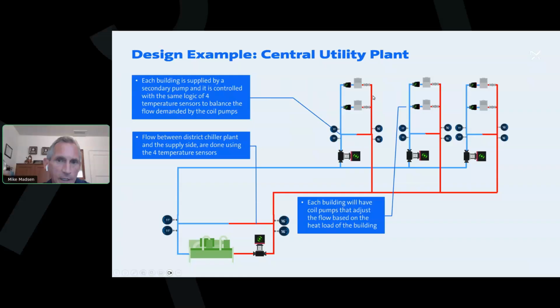So if we converted this close building to distributed pumping and eliminated the control valves, we would push water through the coils if we still had high head pumps here. This is a primary only. Yeah, with a primary only where you're trying to convert some systems. What we have seen some campuses do is, we said you can do it a little bit over time.